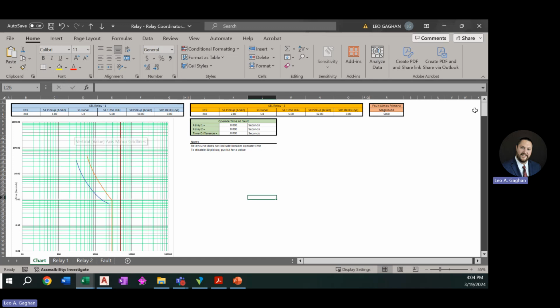And then lastly, this over here, we can see this red line is about 5,000 amps. If we wanted to, we can move that out to 8,000 amps. We can move it into 2,000 amps. Move that fault around. So basically, what we'll be using this tool for in your homework is to coordinate 2 relays, right?